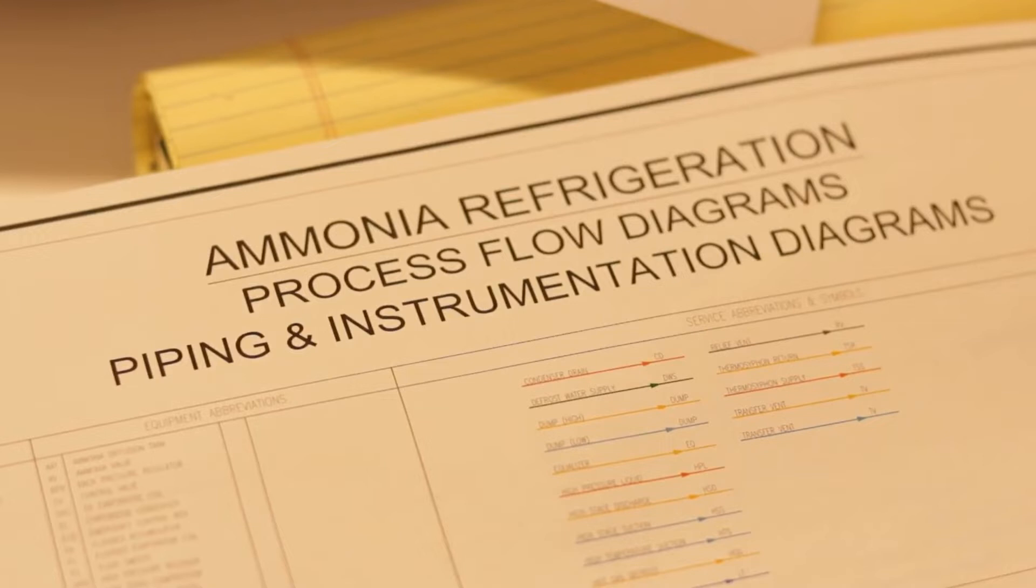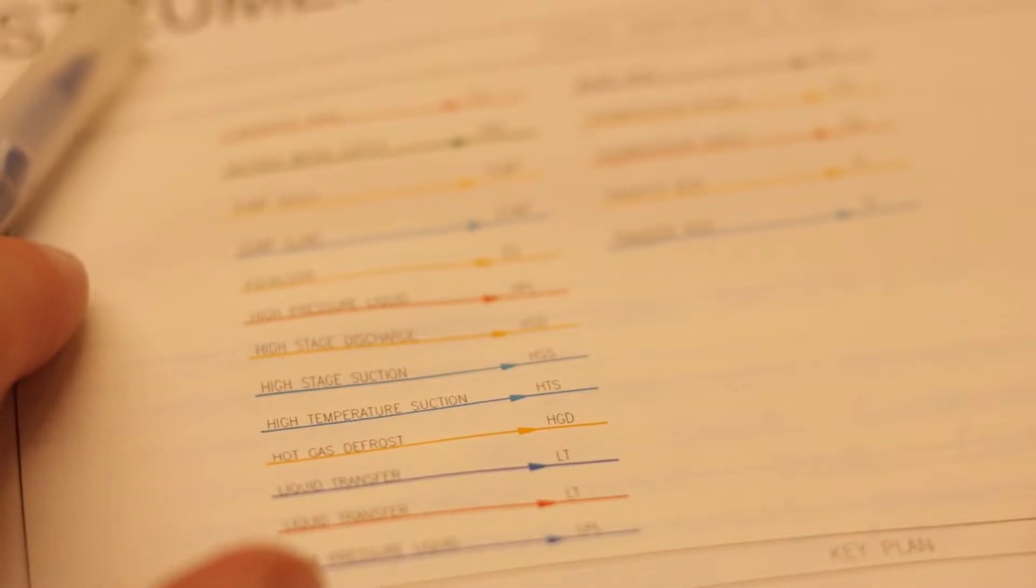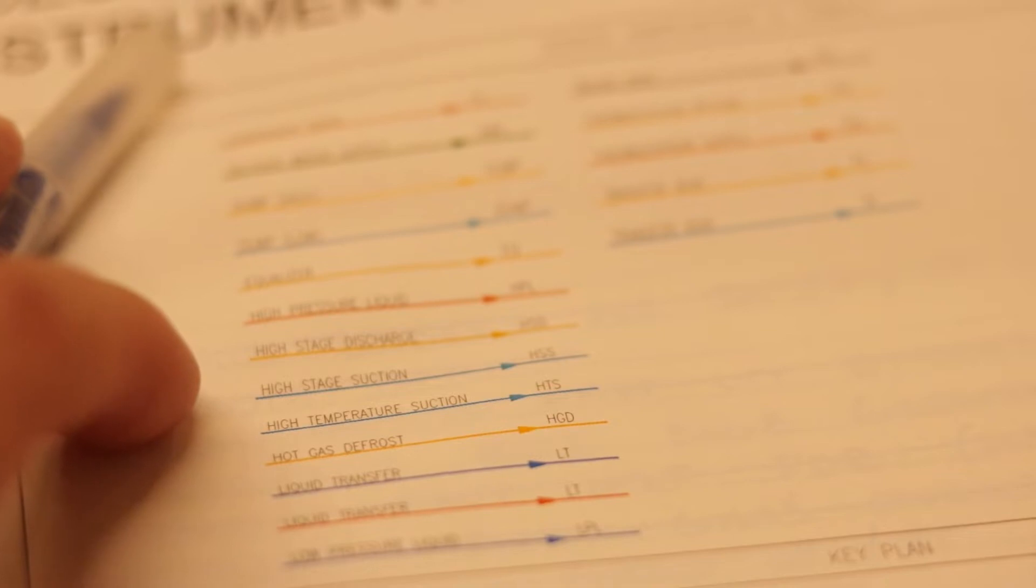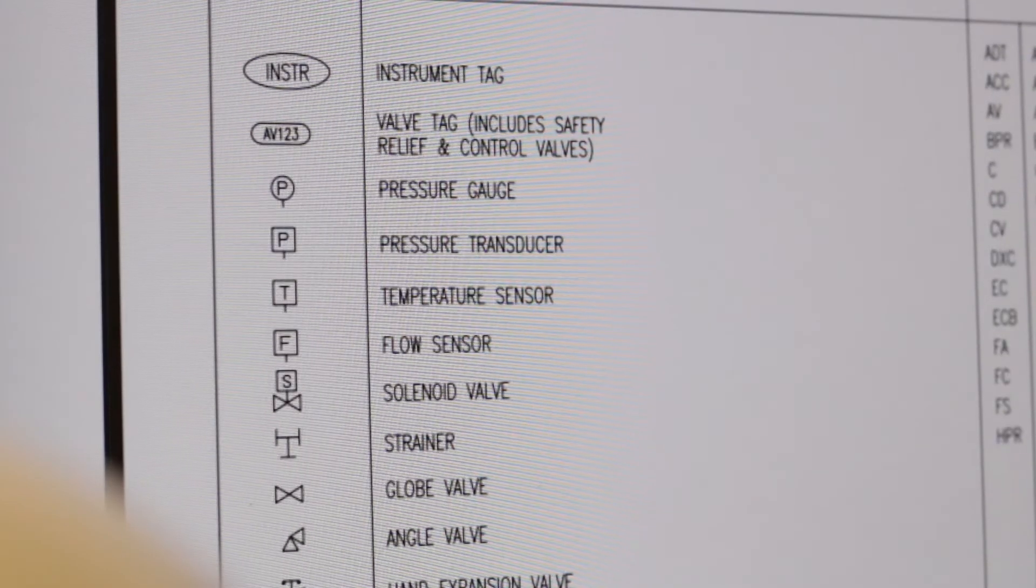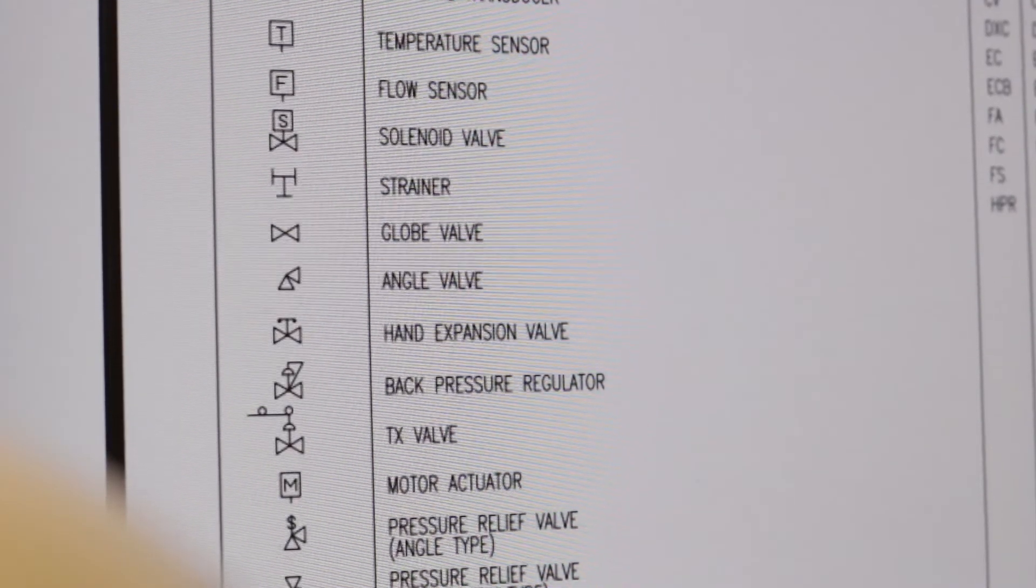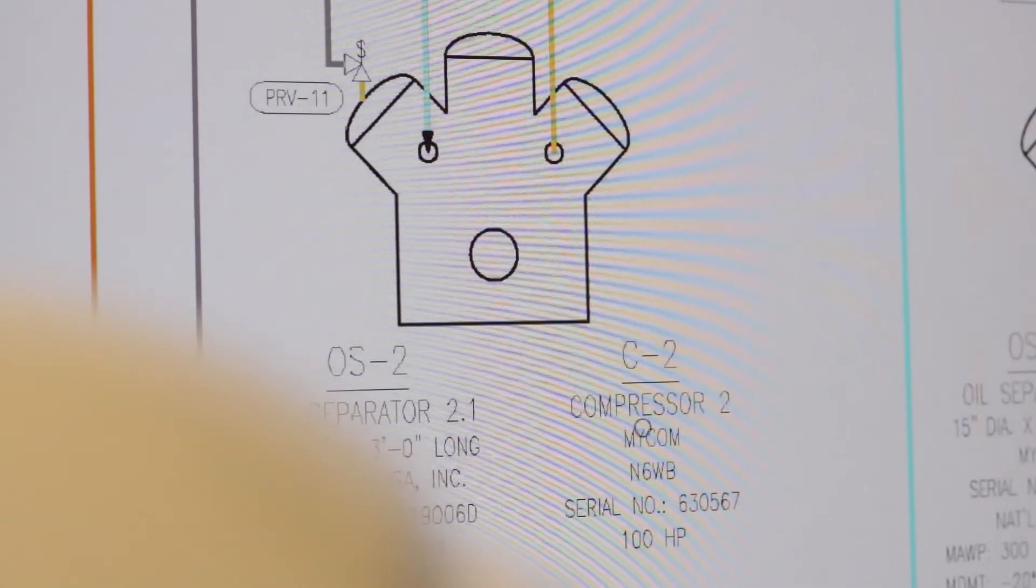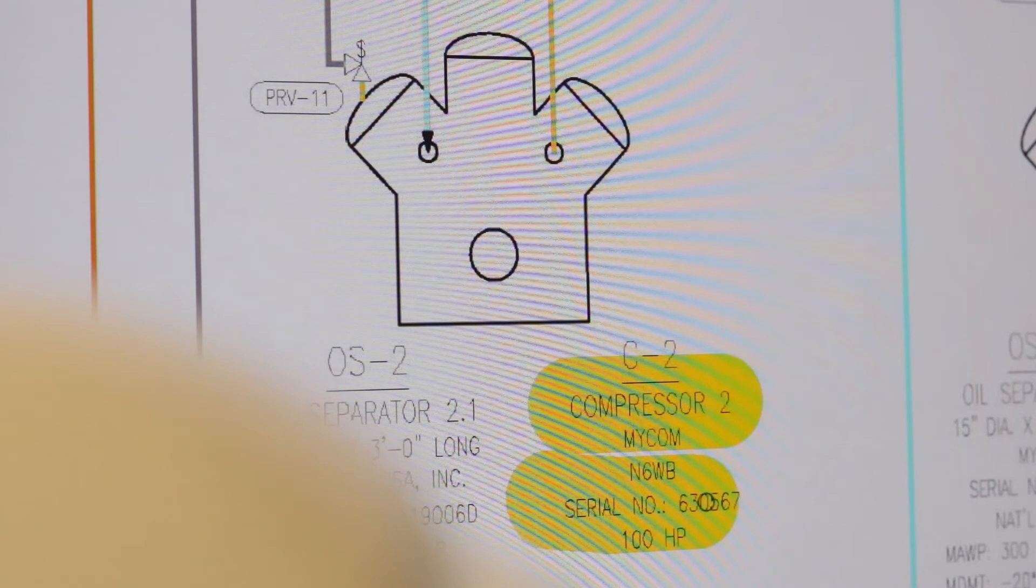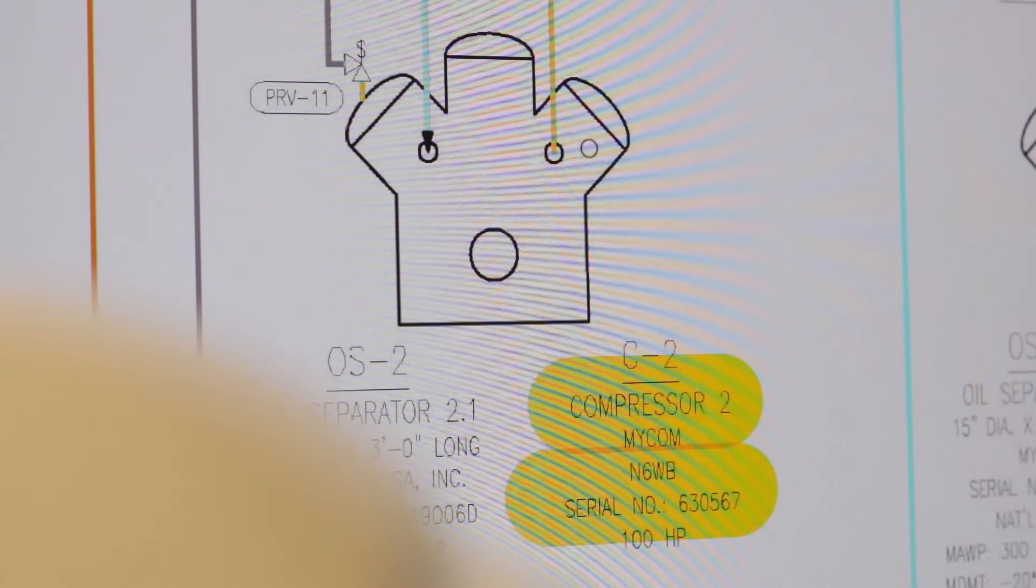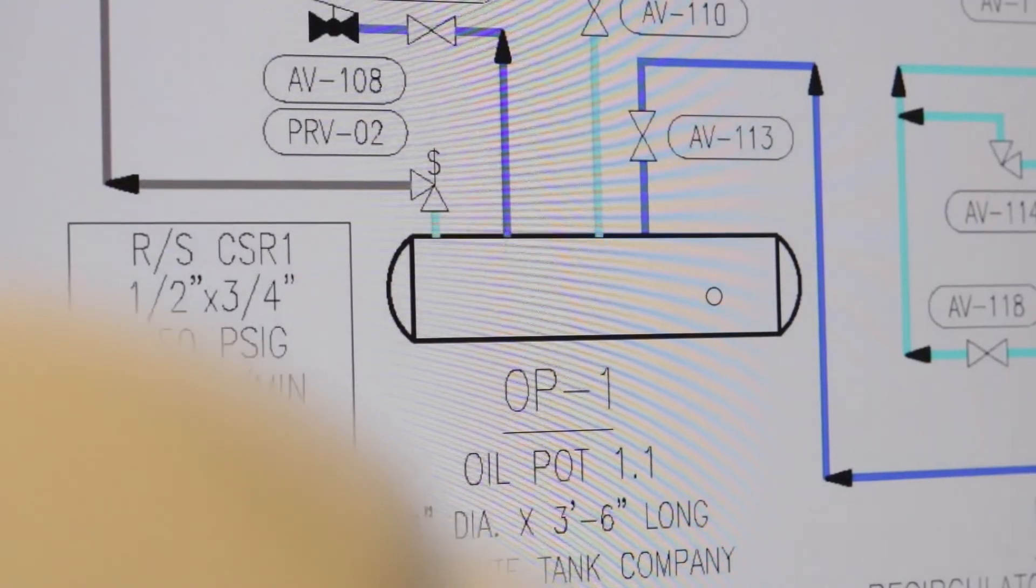A good P&ID will be equipped with a clear legend of symbols to assist in diagram interpretation. P&IDs utilize detailed annotations to describe the pipes and equipment. Examples of typical annotations include equipment name, equipment specifications such as model number, serial number and dimensions.